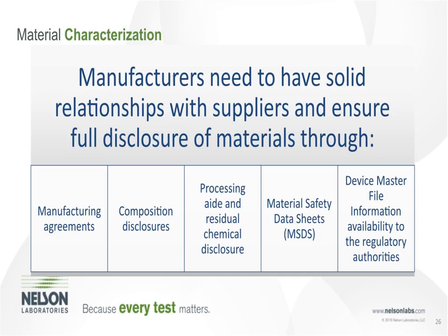And for those of you who are not as familiar with the cytotox test, latex is our positive control. So this is not something that they would have told you had changed, because it was not something that they felt like was a change in the process or in the material, but it could have had a big impact on biocompatibility. So please pay attention and really get detailed as far as your manufacturing agreements.